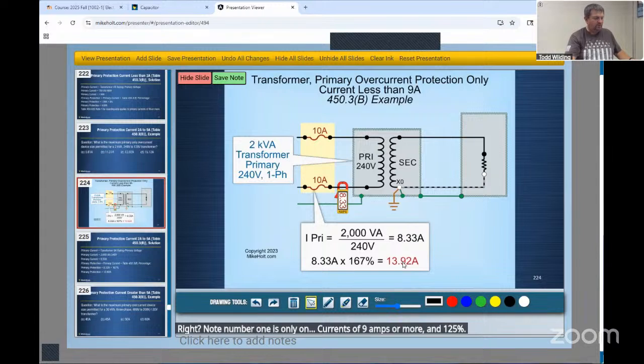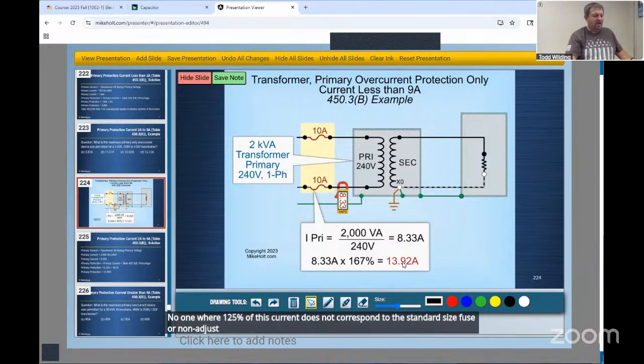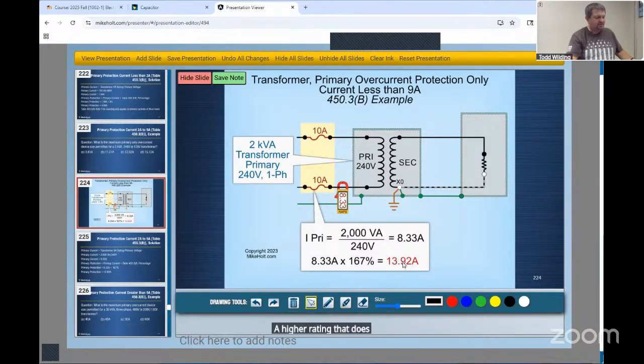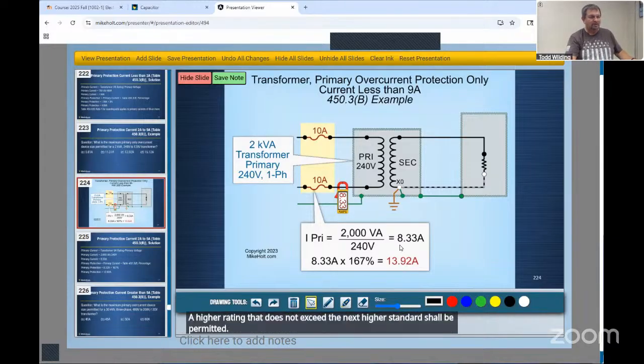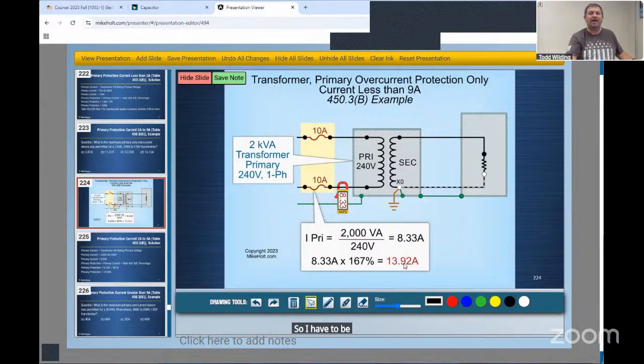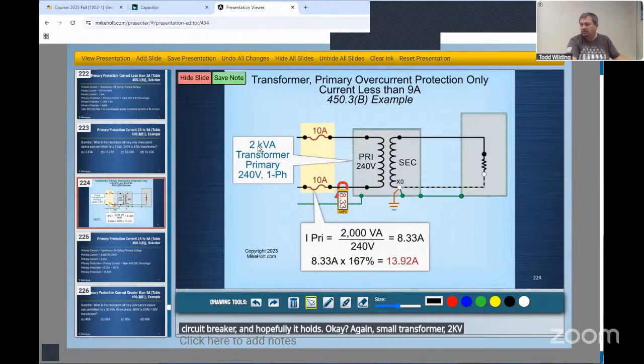Note 1, where 125% of this current does not correspond to the standard size fuse or non-adjustable breaker, a higher rating that does not exceed the next higher standard shall be permitted. So I have to be 13.9 or lower. Standard fuse would be 10 amps, right? According to 240.6. So I'm most likely going to put that on a 10 amp fuse or 10 amp circuit breaker, and hopefully it holds. Okay.